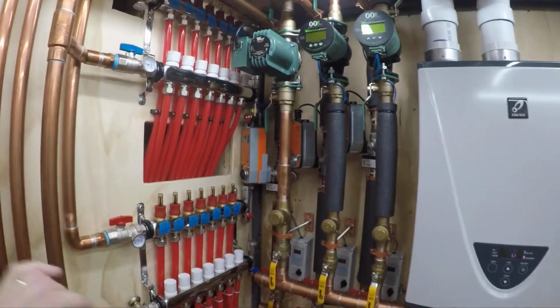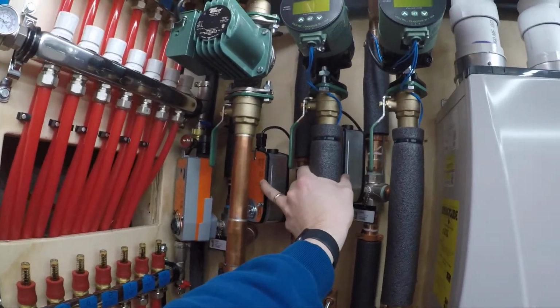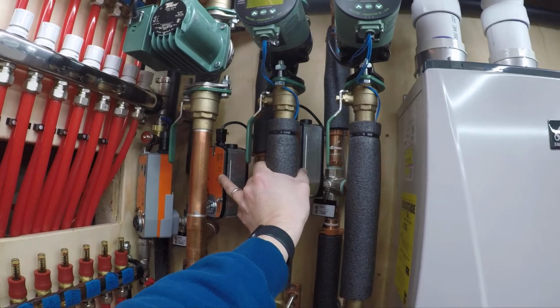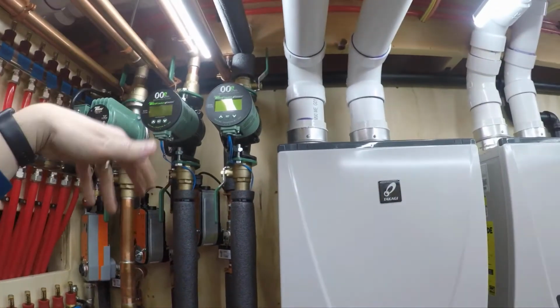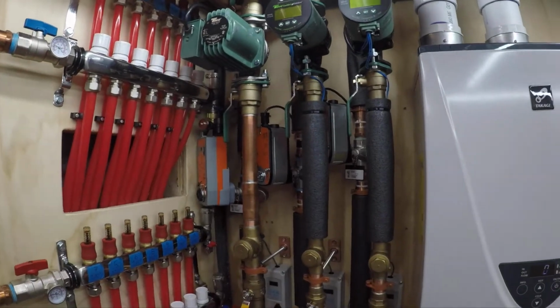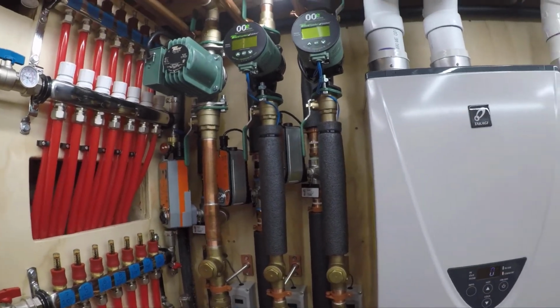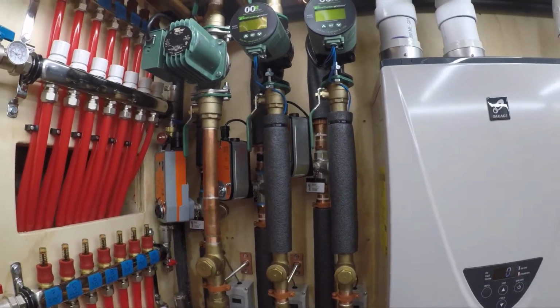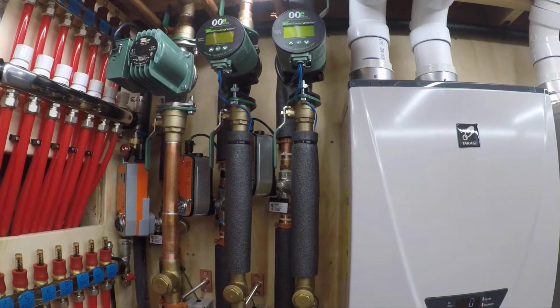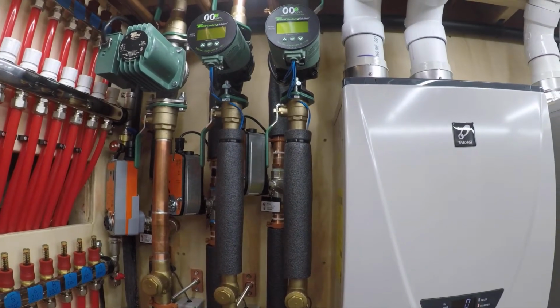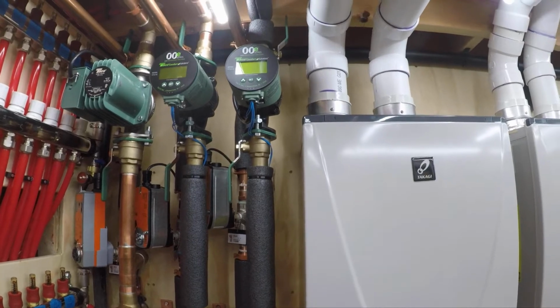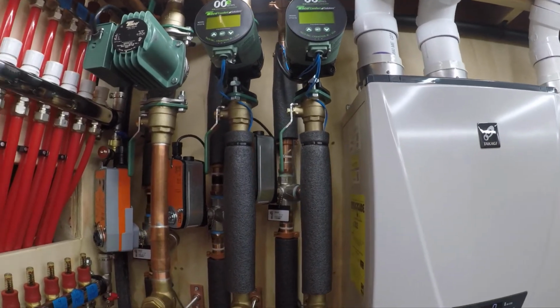Well, without these valves here, these are three-way valves, you could just be dumping heat and heat and heat into like the staple up. And you don't want that. You don't want your hardwood floors to get over 80, 85 degrees. So you can't just dump heat into these rooms that don't need it. You're going to overheat the floors. You're going to overheat the people. It's just not going to be comfortable.